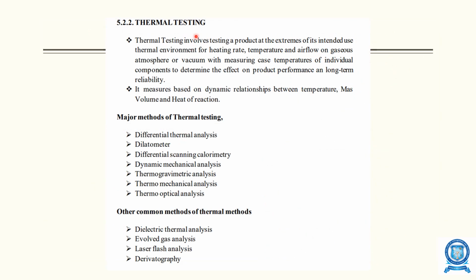Then we are going to see thermal testing. Thermal testing involves testing a product at the extreme of its intended use. So the thermal environment covers heating rate, temperature and airflow, gaseous atmosphere or vacuum, with measuring case temperature of individual components to determine the effect on product performance and long-term reliability. It measures based on the dynamic relationship between temperature, mass, volume and heat of reaction.